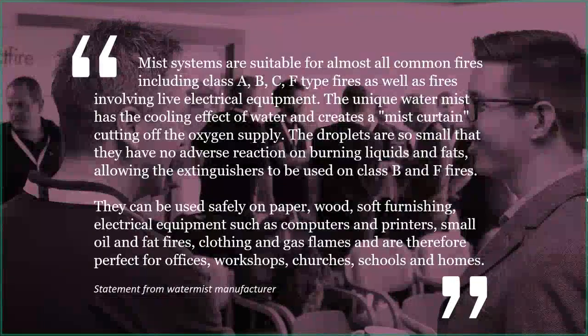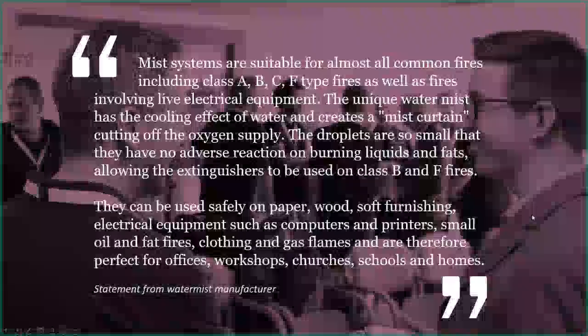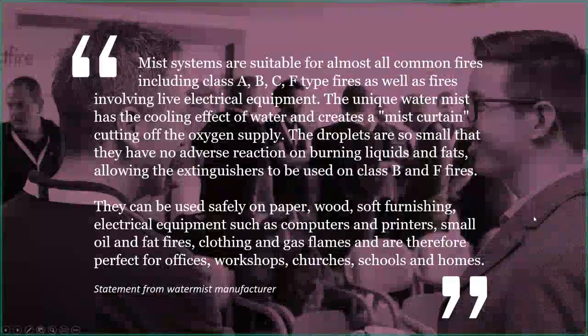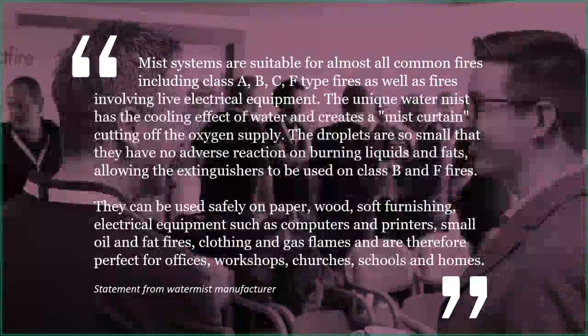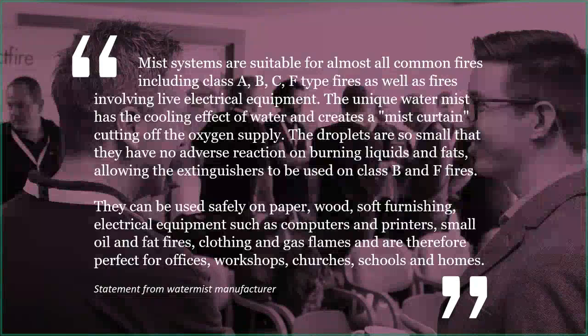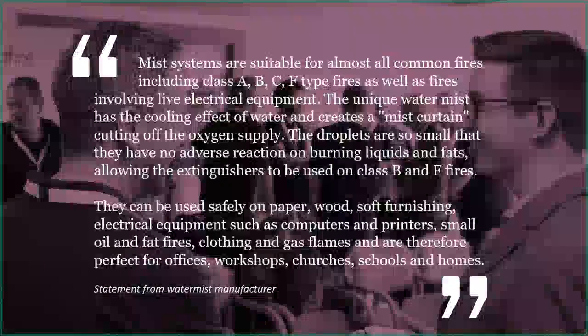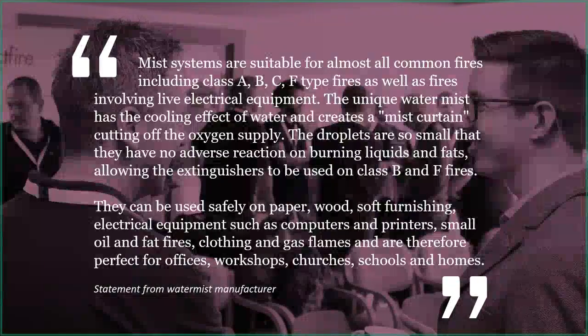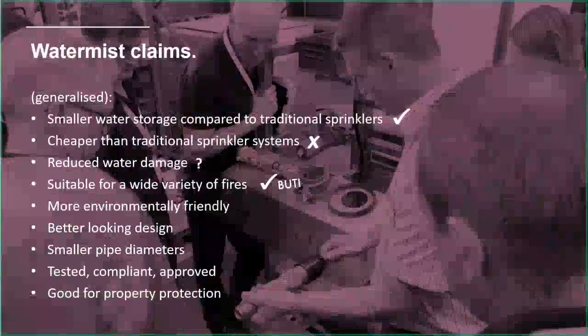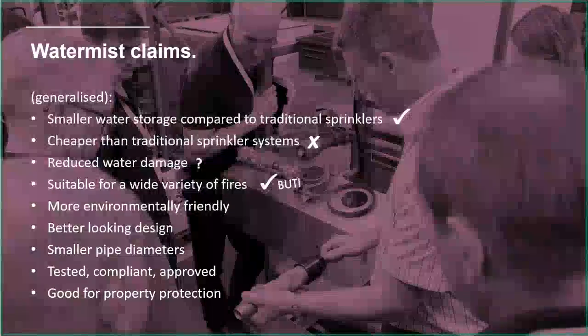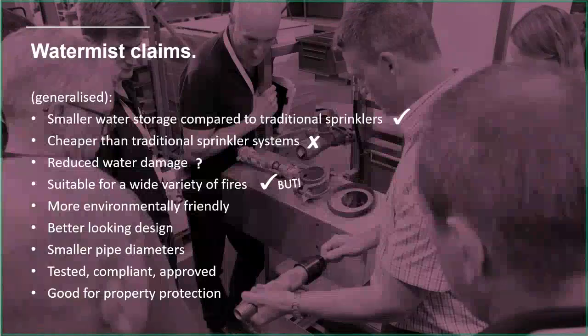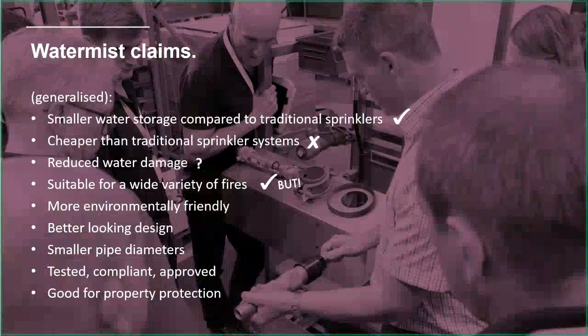But in terms of category A fires, I would still argue that a sprinkler system is better at dealing with category A fires, particularly when you've got storage, lots of cardboard stacked up in racking. The best way to fight that kind of category A fire is to get it wet and get plenty of water on it, which is what a sprinkler system does. So suitable for a wide variety of fires, yes, but is that actually what you want, or do you want a system that's going to be tackling a category A fire?